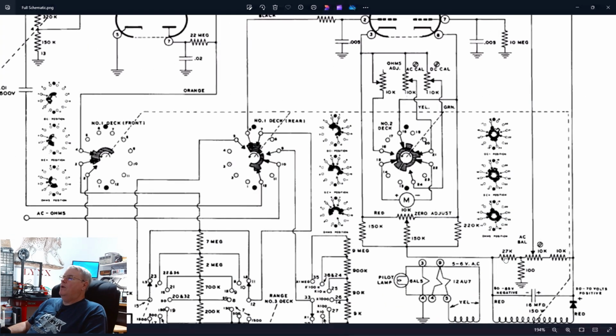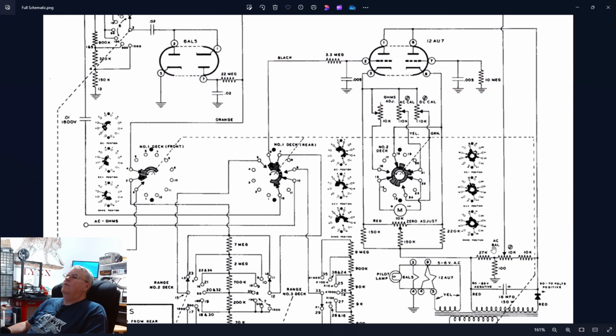One of the calibrations is to do an AC balance. What that does is null out whatever stray potential you generate here when there's no input, by adjusting this pot. It brings it to zero so that all we get back is just our input potential. This is essentially the AC zero adjust—similar to the DC zero adjust, but for AC—and it gets rid of any stray potential here.